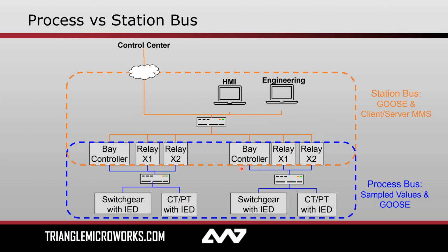In that case, we might include all of our GOOSE on this network, and then certainly all of our sampled values. And then we might have a separate network. Again, it might extend down to these end devices, but a physically separate network that we're using for client-server communications. Now, if someone says they're only doing station bus, that doesn't mean that they're not doing GOOSE, and that's why I wanted to include this on here as well. It just means that they're not doing sampled values. So again, it's a term that the industry has adopted, and I thought it was worth defining.